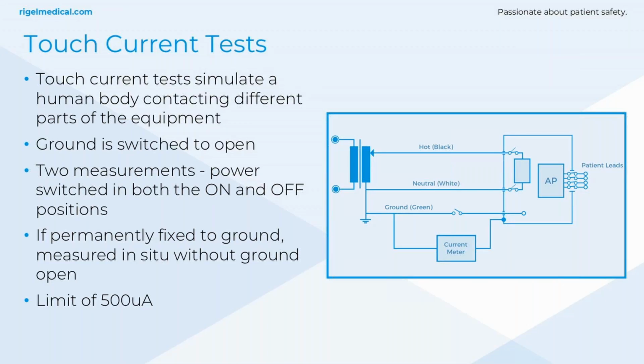And if the appliance is permanently fixed to ground, touch leakage is measured in situ without the ground open. The reason for that is because you can't actually introduce a fault condition if the device isn't connected to the safety analyzer. So what I'll do now is show you a quick demo video of the touch current and ground leakage tests.